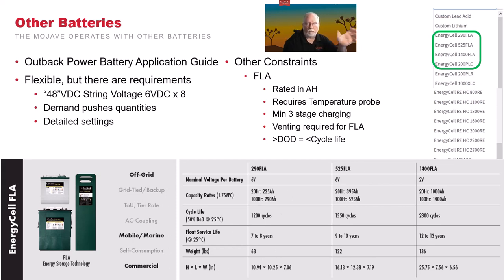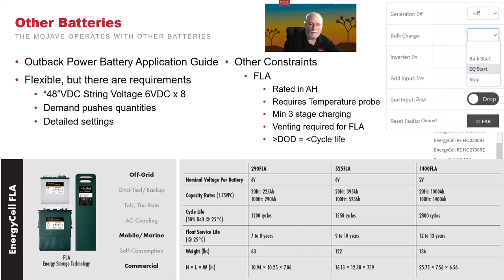These are some of our FLA batteries that we have, the Energy Cell FLAs. Realize that these may be 6-volt batteries, not 12. Therefore, you'd have to put 8 in series. Again, the demand pushes the quantity. They're rated in ampere hours. As being flooded lead acid, you will have to vent them. And one thing to show you is that Mojave does have a function that allows you to bulk start, EQ start, or stop both the functions, so that flooded lead acid batteries are not a problem for Mojave either.